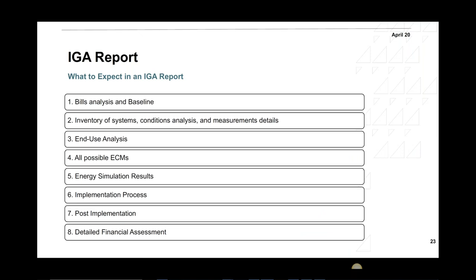IGA report, this is what is normally required in an IGA report. If you go to ASHRAE Standard 211, there's one annex where it shows what should be in the report as an example. You don't have to follow it word by word, but it gives you an example of what needs to be there in an IGA report. Here is also a brief of what needs to be there: bills analysis and baseline, inventory of systems, condition analysis and measurement details, the end use analysis, all possible ECMs, energy simulation results, implementation process, what is required during the post implementation phase, and a detailed financial assessment.